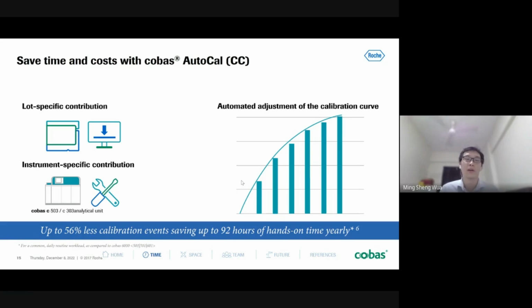The question that people always ask is, does it mean that I don't have to do manual calibration anymore? No. Like I mentioned earlier, if you do a big PPM or change of parts, you will still need to do a manual calibration so that the instrument is able to get this part of the data. Secondly, if after doing the auto calibration you see that the QC is out, as part of the troubleshooting process you can also do the manual calibration. Manual calibration data will override this auto calibration data. Most of the time, you can use auto calibration for most of the assays.